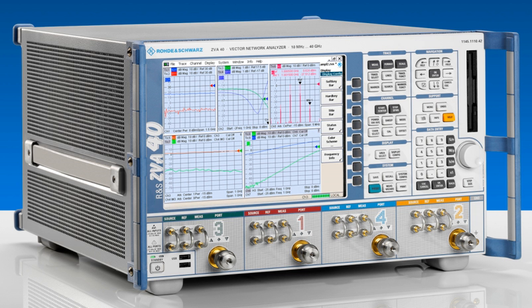A vector network analyzer achieves highly accurate measurements by correcting for the systematic errors in the instrument, the characteristics of cables, adapters, and test fixtures. The process of error correction, although commonly just called calibration, is an entirely different process, and may be performed by an engineer several times in an hour. Sometimes it is called user calibration, to indicate the difference from periodic calibration by a manufacturer.